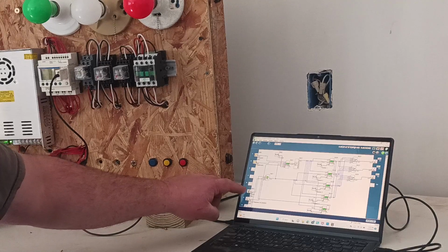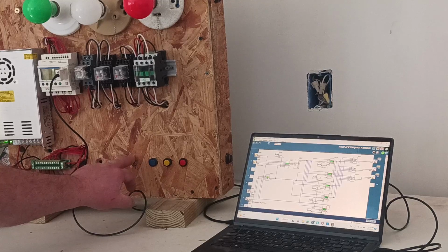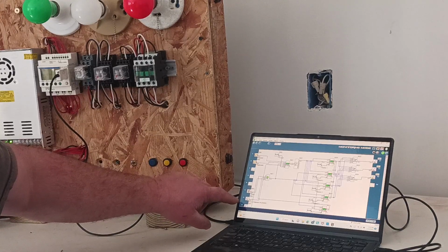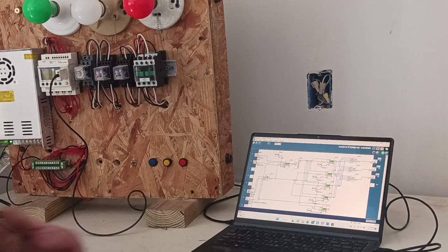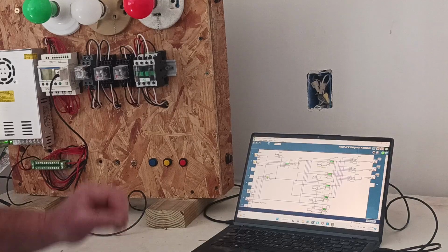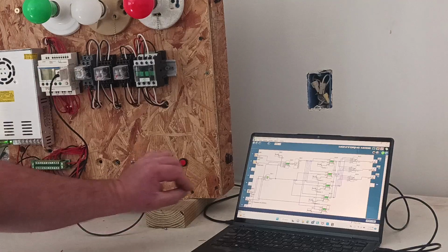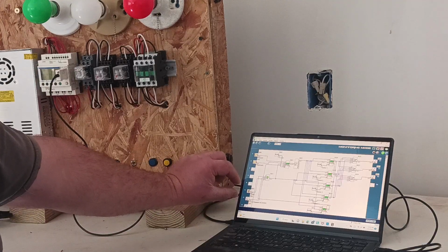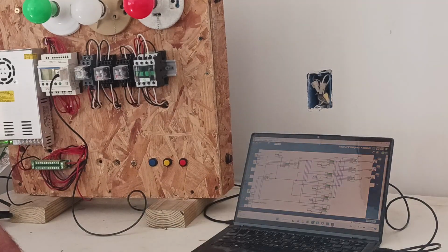Another thing that I have is, of course, a reset, which is our 1C button, which would be here. This would be our reset. Now here, this 1D and 1E, I've kind of set this up to simulate a remote override. Like, you wouldn't necessarily have to hook up 1D or 1E to the PLC itself, but you could have a remote override so that if there's something wrong with a sensor or something wrong with the process, a supervisor could always remotely override it so that you could keep producing your product until it gets fixed.